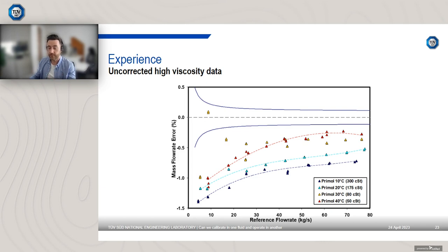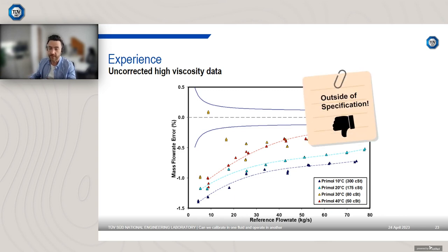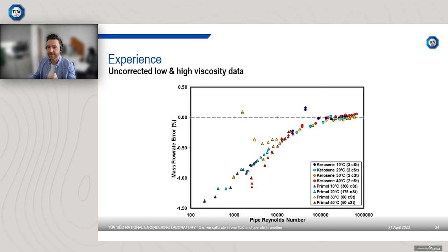Now at this point, back when we completed these results, there wasn't a lot of understanding with respect to Reynolds number effects. Most Coriolis meters were assumed to be unaffected by Reynolds number because they were not affected by installation conditions with respect to upstream and downstream straight pipe lengths, whereas a meter like a turbine device or ultrasonic might need 5, 10, 20 diameters upstream and 5 diameters downstream. Coriolis meters are not affected by the entry lengths, however they do appear to be affected by viscosity and Reynolds number effects. I'll show you that in the next slide. So the meter is out of specification, obviously that 0.1%, all but those two rogue points at 10 kilograms a second at 30 degrees Celsius, just by chance.